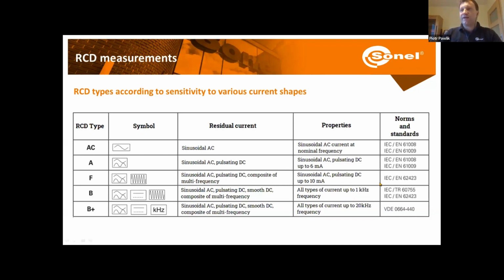So that's why we have RCDs of type A, which work with sine wave AC and pulsating DC up to 6 milliamps. We have type F, which works with sinusoidal AC, pulsating DC, and composite of multi-frequency up to 10 milliamps. B type works with the sine wave, pulsating DC, smooth DC, and composite of multi-frequency up to 1 kilohertz. And B plus, same as B, but up to 20 kilohertz.